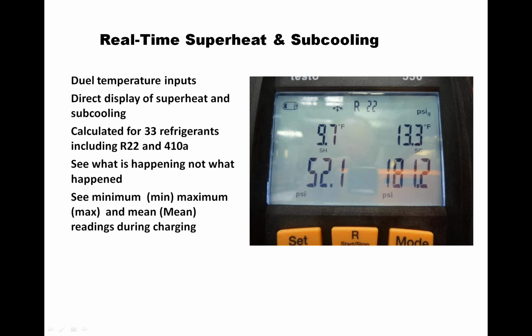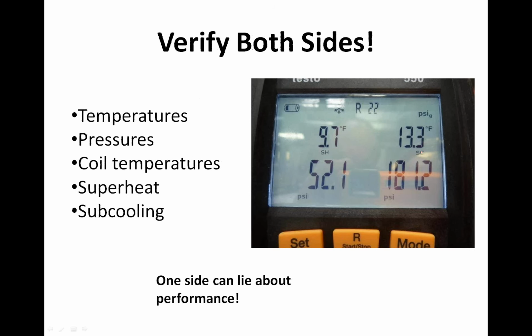And if I have a system that's hunting a little bit, I can use the min-mean-max function to see what the minimum superheat was, the maximum superheat was, and then at the end, see what the average is of those readings. So it makes it very handy. You've got to make sure you verify both sides: pressures, temperatures, coil temperature, superheat, and subcooling, because one side will lie about performance. Okay, we can't just go, oh, it's a TXV, I'm going to get the subcooling correct and walk away. You don't know for sure that that TXV is operating properly. It could have a loose bulb. It could have a defect in installation. You've got to check both sides of the system. Same thing with a fixed orifice before we can walk away.